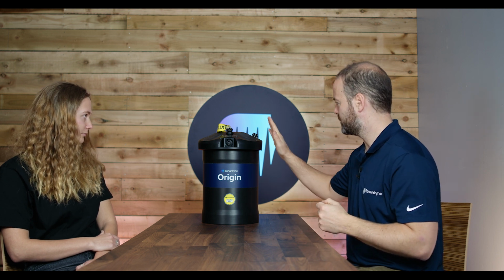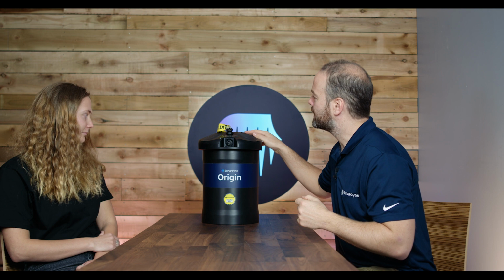We've also got a fast charge port, again on one of the sloped edges of the end cap. Once the device is back out of the water and it's depleted its internal rechargeable battery, you then plug it into mains using a kit we supply with the ADCP, and that will fast charge the ADCP. It normally takes about 4 hours or so to reach 80% charge, so it is quite quick. So that's another external connector.